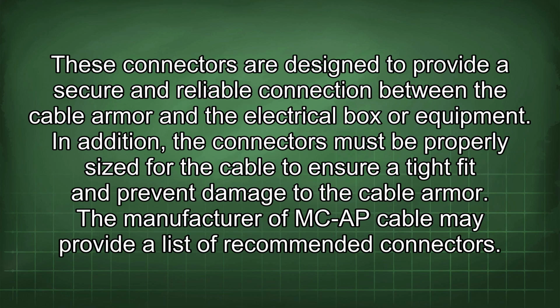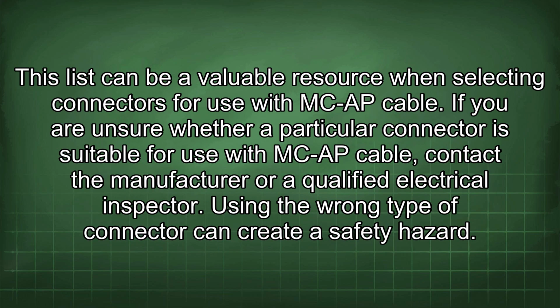These connectors are designed to provide a secure and reliable connection between the cable armor and the electrical box or equipment. In addition, the connectors must be properly sized for the cable to ensure a tight fit and prevent damage to the cable armor. The manufacturer of MCAP cable may provide a list of recommended connectors. This list can be a valuable resource when selecting connectors for use with MCAP cable.